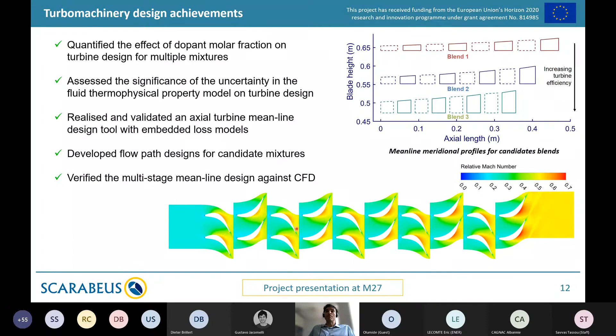Moving to the heat exchanger, this focuses on two different heat exchangers. The first is the air-cooled condenser, which has to deal with the CO2 blend in condensing phase and with high ambient temperature, and the recuperative heat exchanger for the cycle, which also has to deal with the blended CO2. Both are specifically designed for the blended CO2.